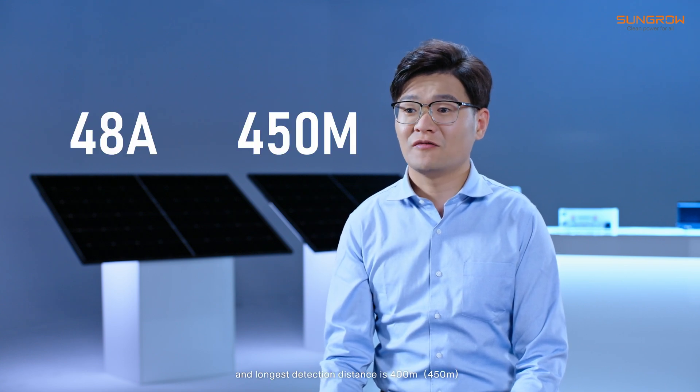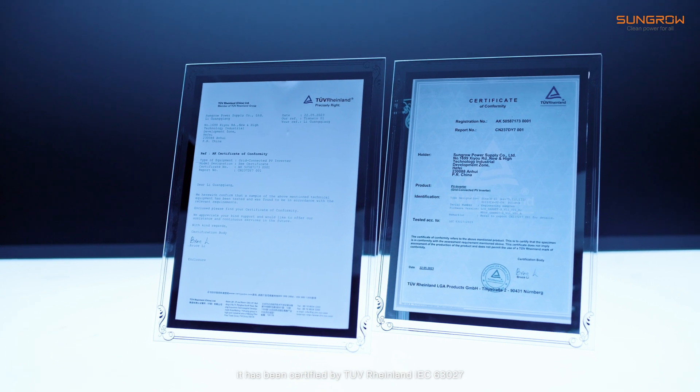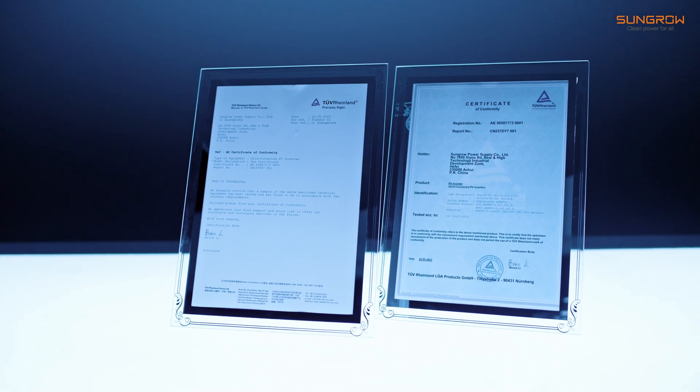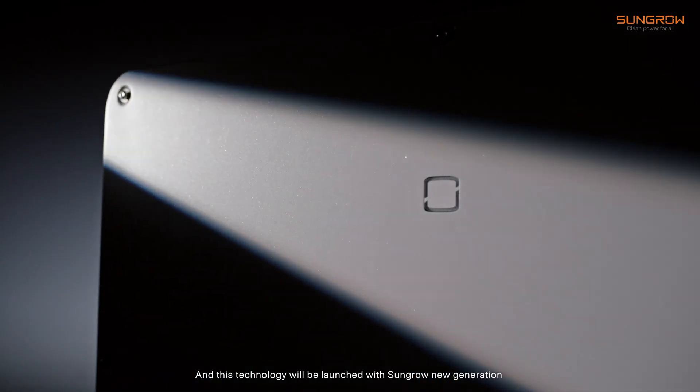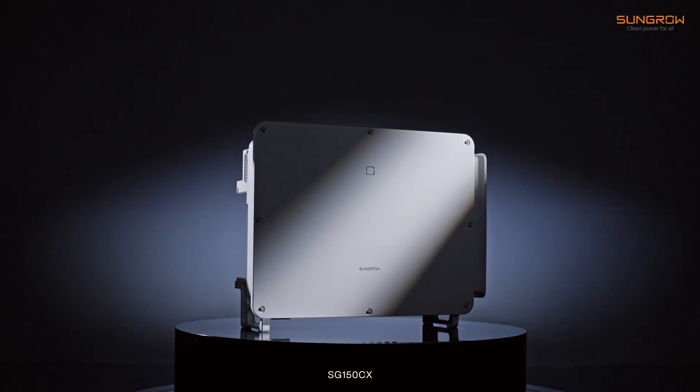The maximum detectable current is 48 amps and the longest detection distance is 450 meters, to meet all PV scenarios. It has been certified by TÜV Rheinland IEC63027, and this technology will be launched with the SunGrow new generation high power string inverter SG150CX.